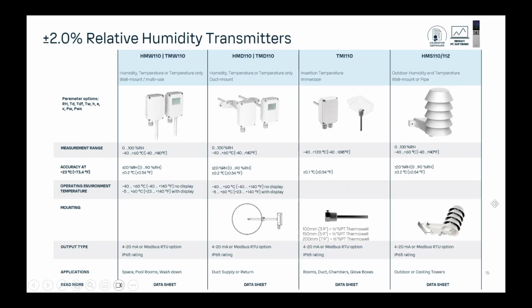This duct-mounted probe still offers the adjustable insertion depth, so you have one probe length, but this finning piece will allow you to move the probe in and out for different size duct diameters. And then over in the middle on the right is a transmitter that's been gaining some traction recently in the data center market. This is our TMI 110 immersion temperature.